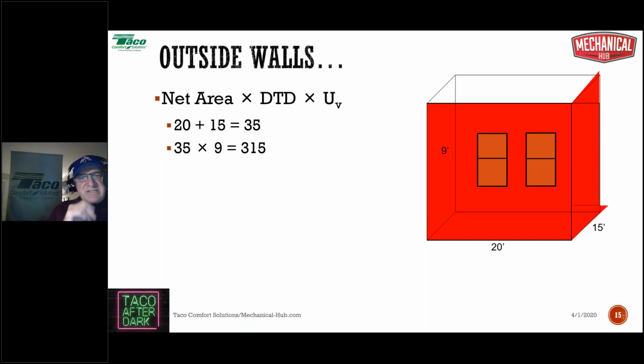Now let's take a look at this. We've got two outside walls, one of them's 20 foot long, one of them's 15 foot long. Make our lives a little bit easier, let's just presume this to be one long wall. 20 foot plus 15 foot, that's 35 feet worth of outside wall. Again, keep it simple, make it one big long outside wall. 35 feet times 9 foot tall, that's giving me 315 square foot of outside wall area, gross wall area.